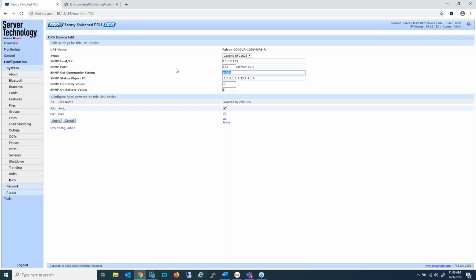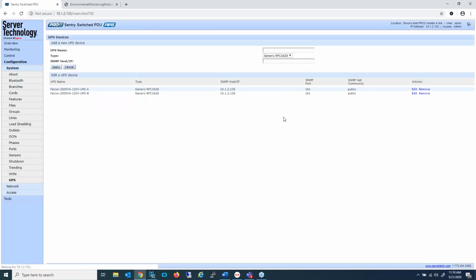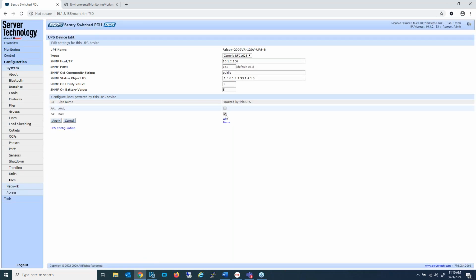Public tends to be the default get community string for most devices. If you have changed the community string on your upstream UPS, you need to change that value here in the PDU so that it matches. Beyond that, you need to then tell the system, in this case, again, this system is a master PDU identified as the A PDU and a link PDU identified as the B PDU. You need to tell the system which UPS is powering which PDU. My A UPS is powering my master PDU, so I previously clicked that box and clicked apply. And for the B PDU, I went in and told the B PDU, the link PDU, that the UPS B is powering this system. So UPS B powers the link unit, UPS A powers the master unit, and that completes the configuration for UPS setup. This allows the PDU to go out and query the UPS every 10 seconds for whether or not it is on battery versus on utility.